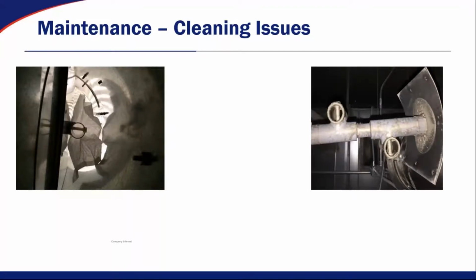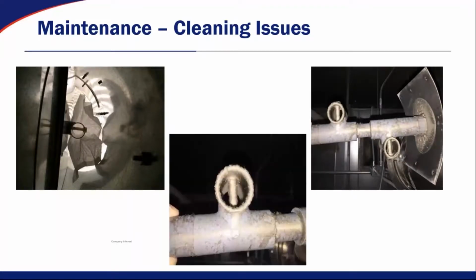This is another example of a general exhaust flow sensor, same type of vortex shedding technology. And what happens is when you get a lot of buildup on that sensor, not only can the pressure ports on it get clogged up so you can't read it, but as you change the diameter of that tube, it's going to change the velocity of air going through there, which is going to put an offset on your accuracy.